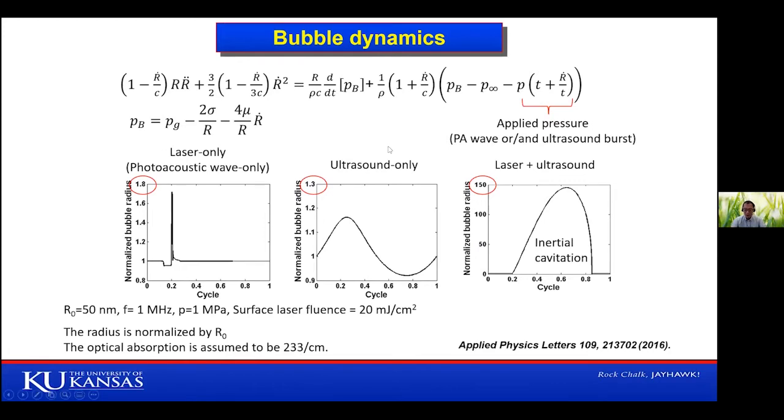And when you push that away, of course the water works like a spring. When you push it away, it will come back. When it comes back, because the water has a very huge density, you're going to see this huge collapse here. So it can produce very strong mechanical force when it collapses, and so that's of course going to do some mechanical damage in that spot.